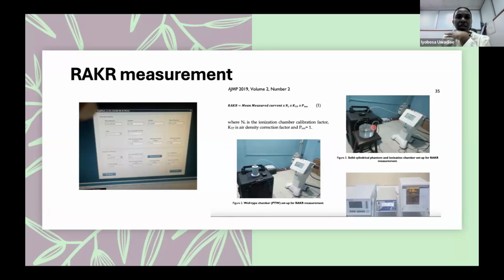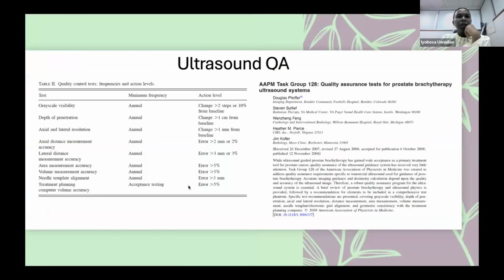So we have three different detectors that we use for our reference air kerma measurements. We have actually done a study that compared the three of them, and they are very, very comparable. So whichever one is available for use. Then another very important QA test is the ultrasound for the ultrasound system.